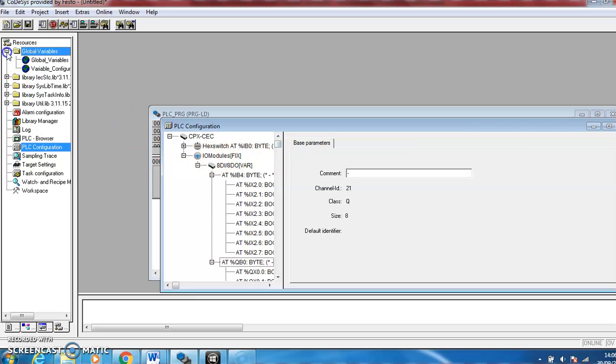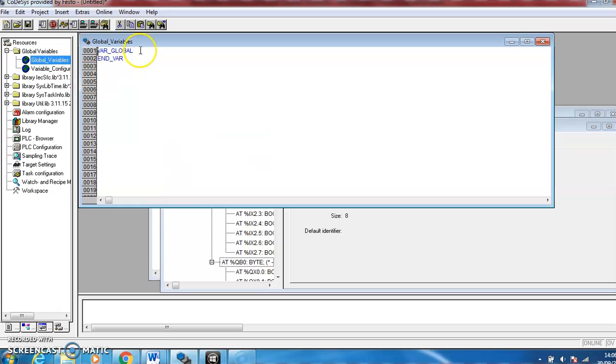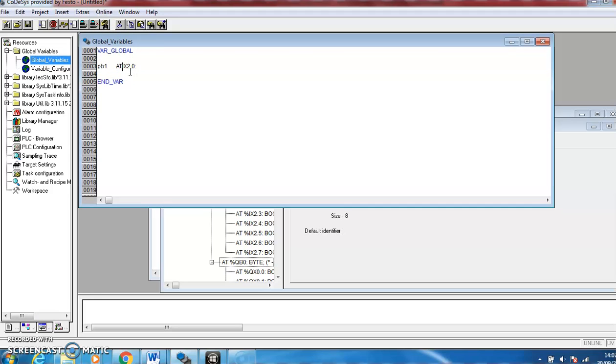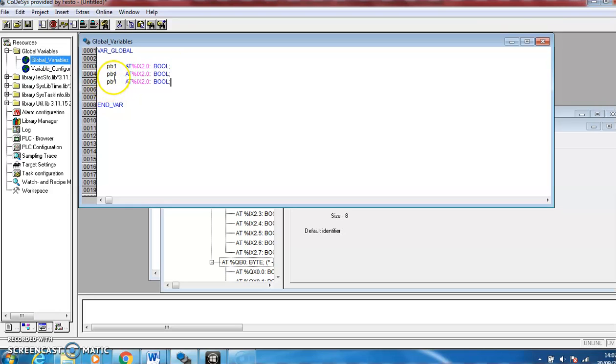So we can then go and create our variables. We know that we have inputs, three buttons. So PB1 is the first button and it's addressed to the first input. I need a percentage in there, that percentage IX 2.0 colon, and then I have to say what type of variable it is. It's a boolean style variable and we need three of these, so you can copy and paste as long as you make sure and change the names and change the addresses.